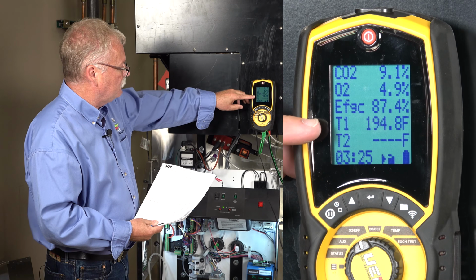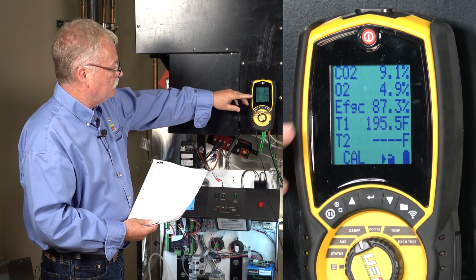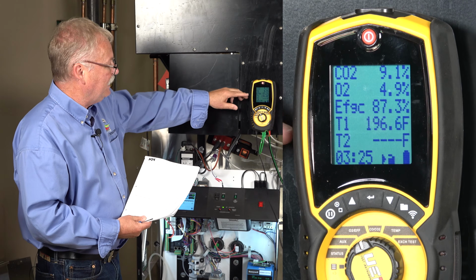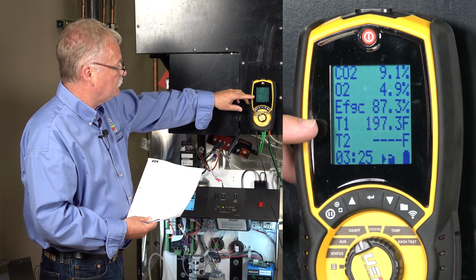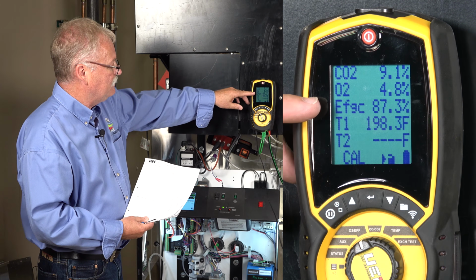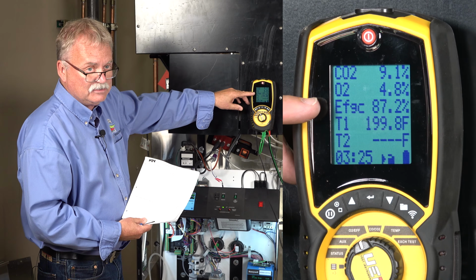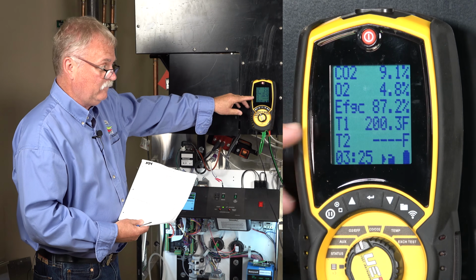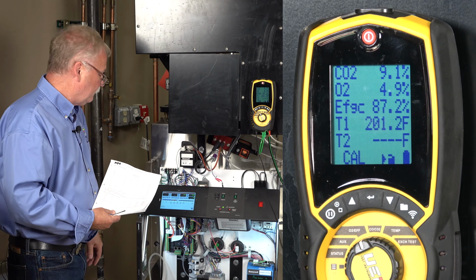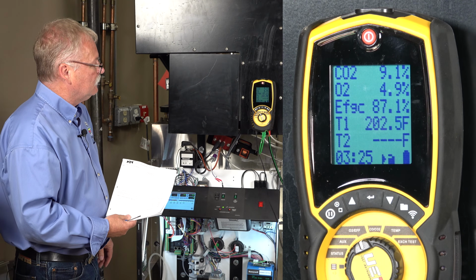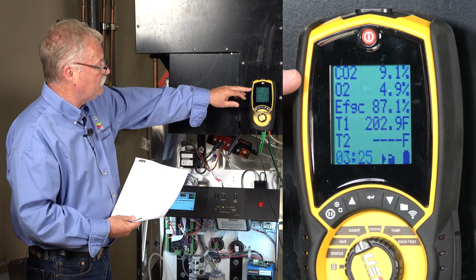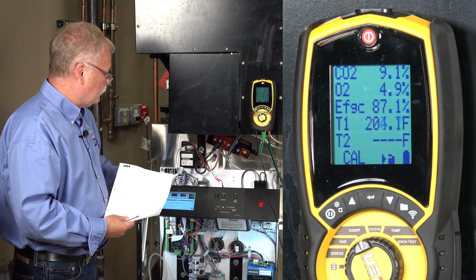As you can see, the temperature is going up because we're still moving the same amount of water, so we can't take as much heat out, so the flue temperature goes up. That means our calculated efficiency is going down. All right? I'm not really worried about these numbers right now, the CO2s, but I just want to see where we're at.